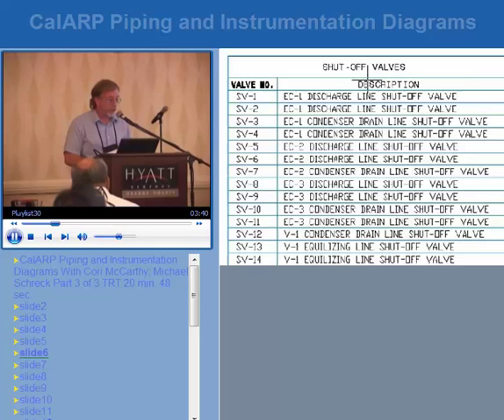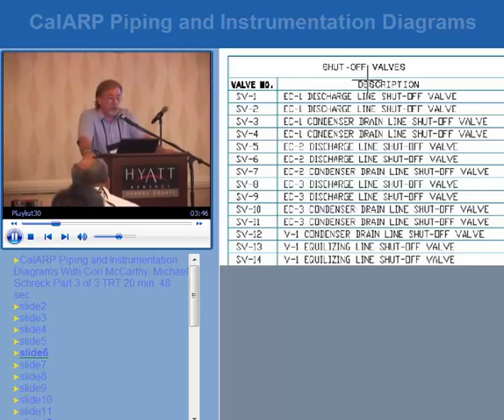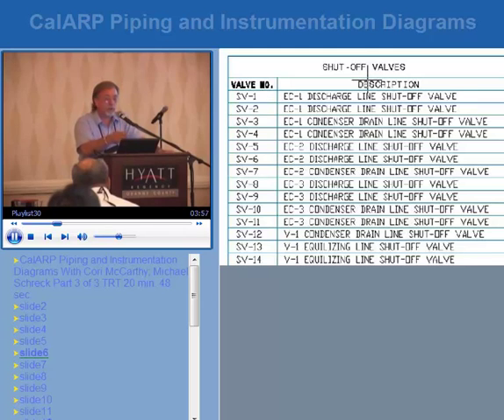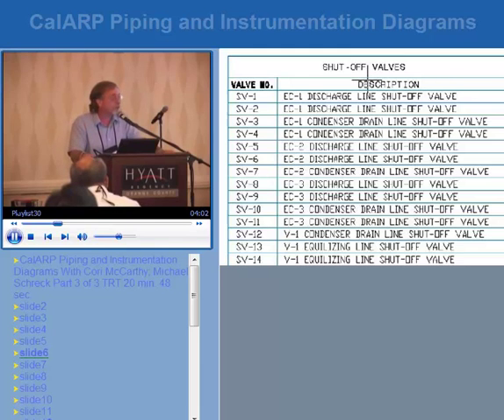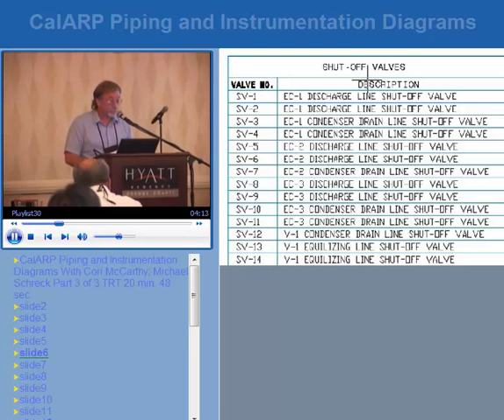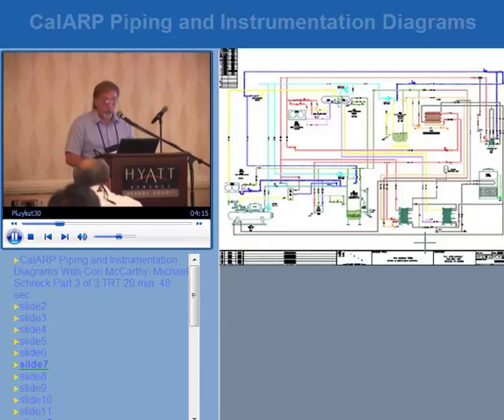You will find many P&IDs that do not have valve tag numbers. Once valve tags are in place, they should have a valve list. This company put valve numbers in flow order — SV1 was the first valve, the next was SV2, and so on. The list says it's located at EC1 and is the discharge line shutoff valve. If the drawing were complete, you should be able to locate a valve tagged SV1 on that discharge line.